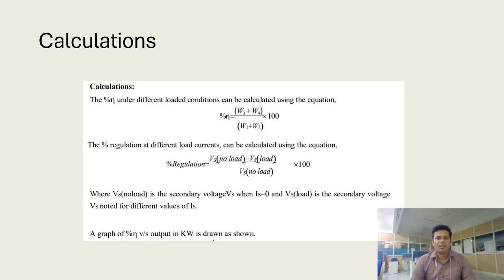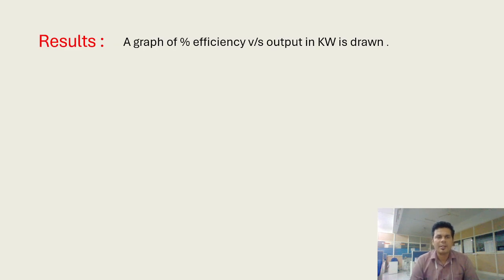These come under your calculation formulas. For efficiency, it is (W3 plus W4) divided by (W1 plus W2), into 100. For regulation, we use (E0 minus V) divided by V, into 100, or you can say (Vs no load minus Vs load) divided by Vs no load, into 100. That will give the regulation. And finally the results: we are going to plot the percentage efficiency versus the output in kilowatts. Thank you.